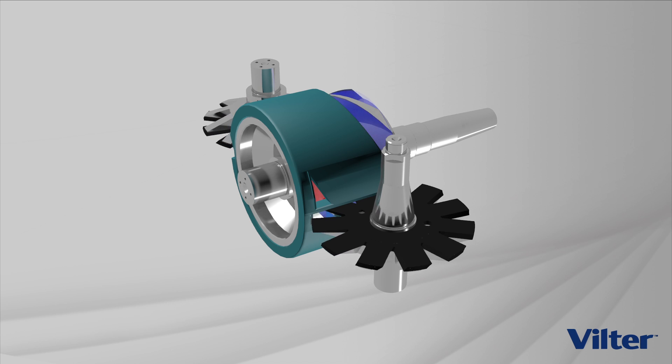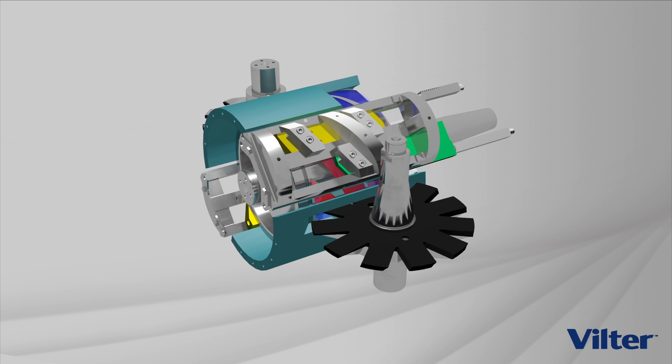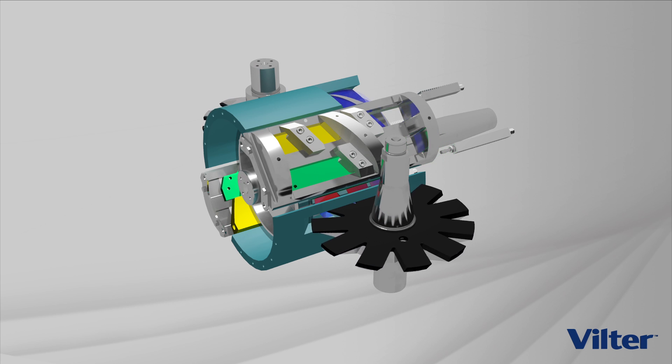Rather than fixed suction and discharge ports, the Vilter single screw has parallel slide valves, which allows infinitely variable capacity and infinitely variable volume ratio at all operating loads and conditions.